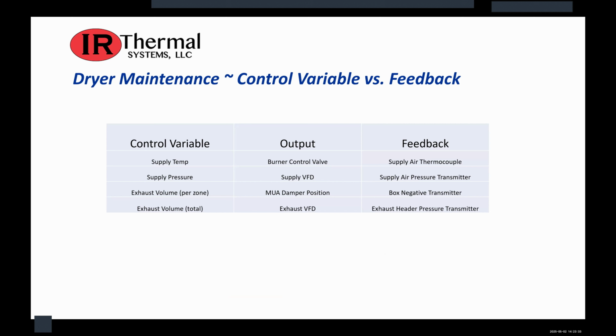This is a simplistic idea, but I don't think people study it enough. It's how the control variables versus the feedback work. A lot of people don't understand that when I'm controlling the supply temperature, the device that's actually controlling that supply temperature is a butterfly valve on my burner. So whether that opens and closes controls the rate of burn of natural gas within my system.